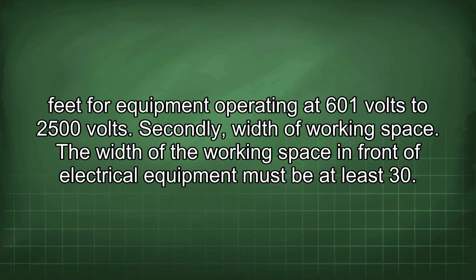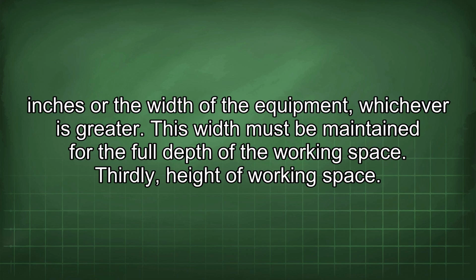Secondly, width of working space. The width of the working space in front of electrical equipment must be at least 30 inches or the width of the equipment, whichever is greater. This width must be maintained for the full depth of the working space.